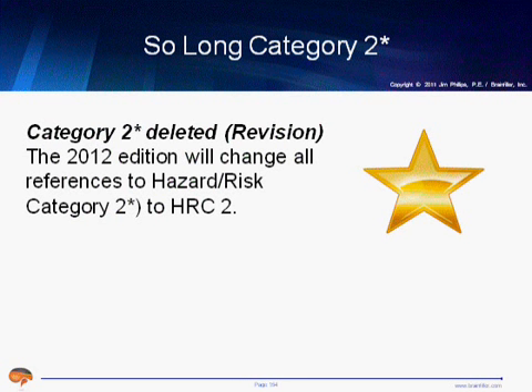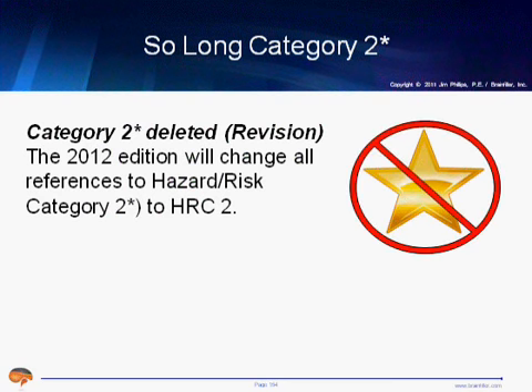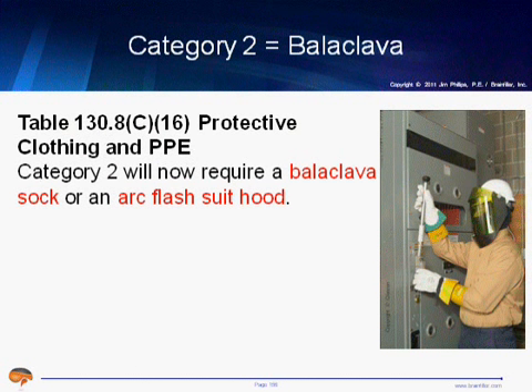Category 2 star, this is another area that's caused some confusion, because I know many people recognize that sometimes the term category is equated to 8 calorie per square centimeter, and then you see 2 star and you scratch your head and think, well, where does that fit in? And 2 star is actually just a function of the hazard risk category tables. Well, beginning with the 2012 edition, the star is going away. All you're going to see is category 2. And the new requirement, Category 2, is now going to require the balaclava sock or an arc flash suit hood. So 2 star goes away.